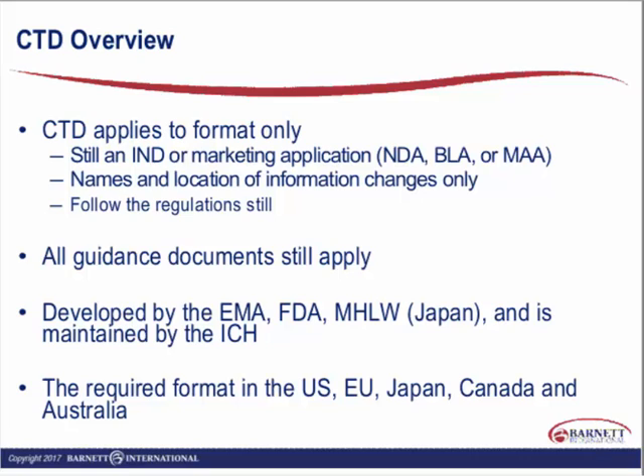The important thing to know is that the CTD, or Common Technical Document, applies to format only. You're still submitting an IND, or an IDE if you're using it for devices, or the same marketing application — it's still going to be an NDA, a BLA, or an MAA. It's just that the names and location of the information changes. You still have to follow all the regulations and you're still providing the same information. It's just where you put it that's the biggest difference. All guidance documents apply, so you have to make sure that you're up to date with the guidances.